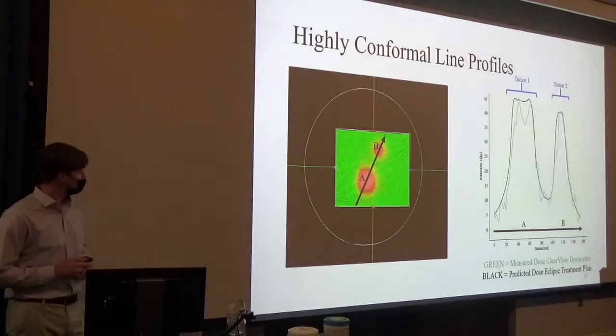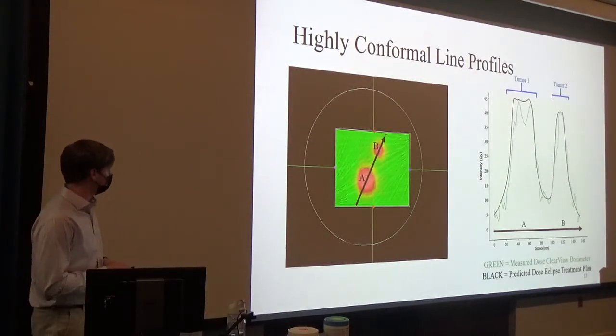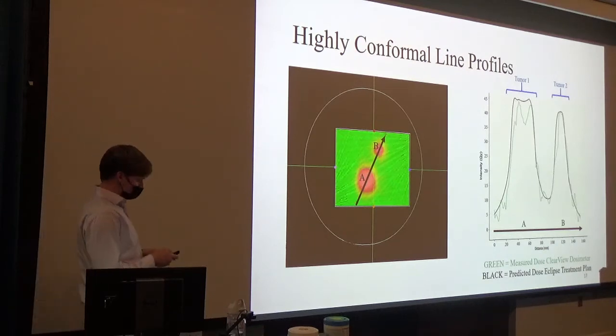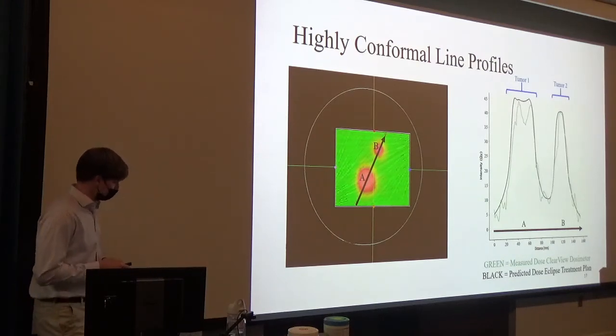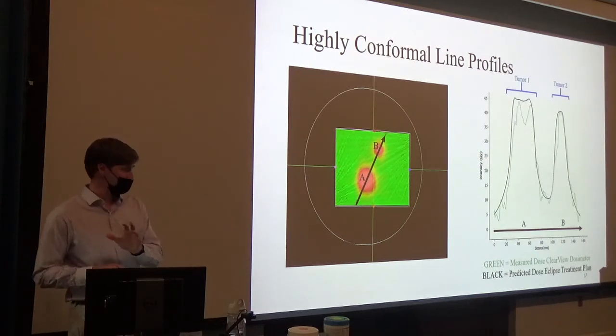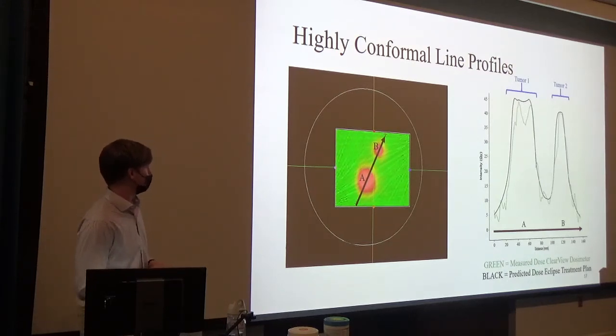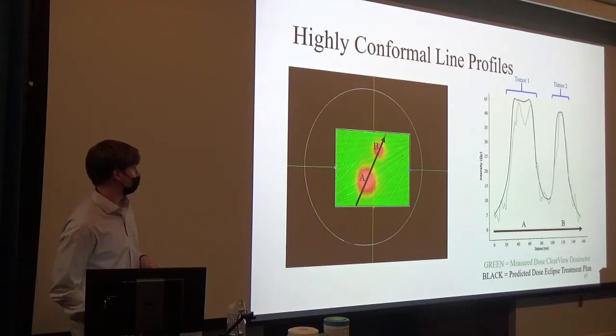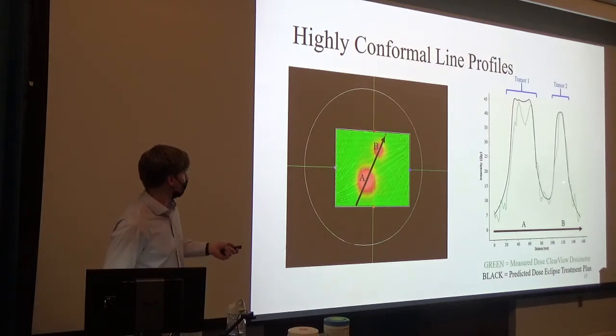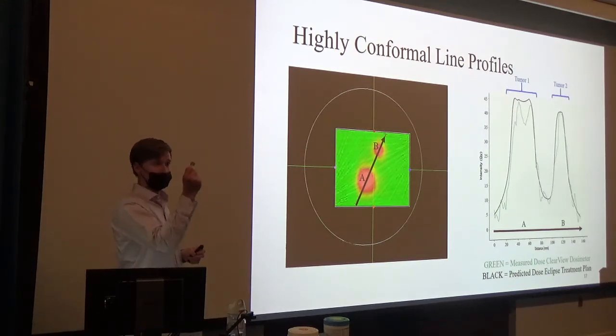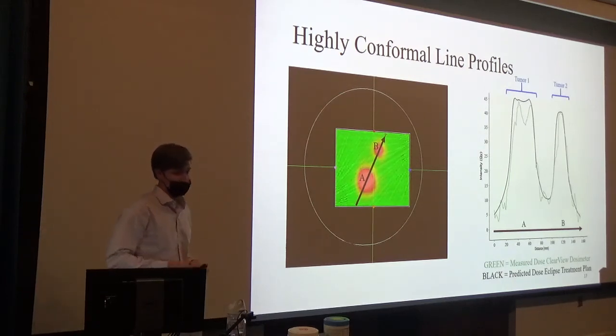In addition to gamma analysis, we can also extract line profiles. The image is interpreted by following the black arrow moving across, which corresponds to the line graph moving left to right. Our first tumor target is represented here, and the second with B on the right side. In the line graph, green shows the measured dose from the Clearview dosimeter we scanned, compared to the predicted dose from the Eclipse treatment planning system. It's very conformal across both tumors. What I think is even more impressive is the distance between the two tumors — we can drop from 45 Gray all the way down to 10, and the physical distance between those two tumors is the size of a quarter, which is quite impressive.